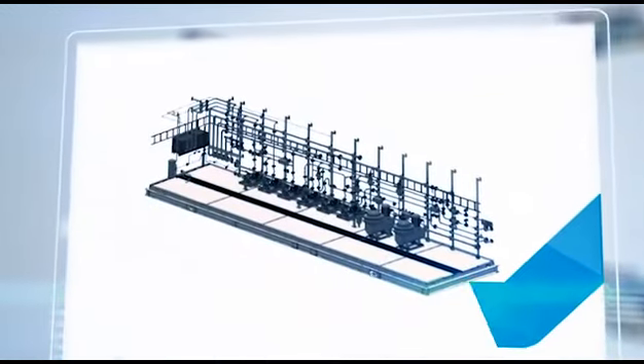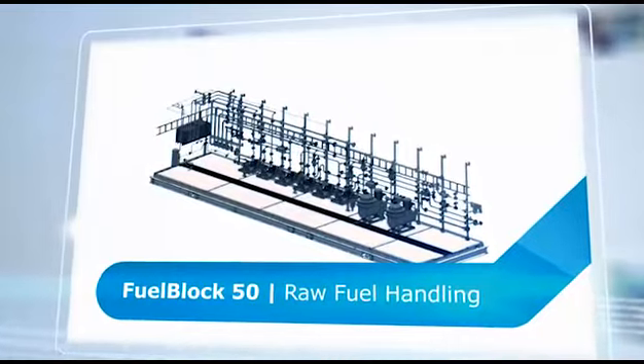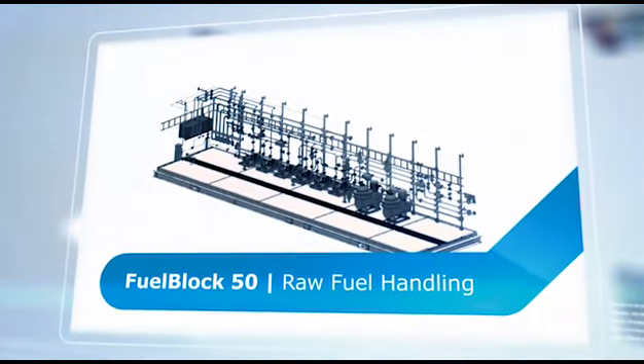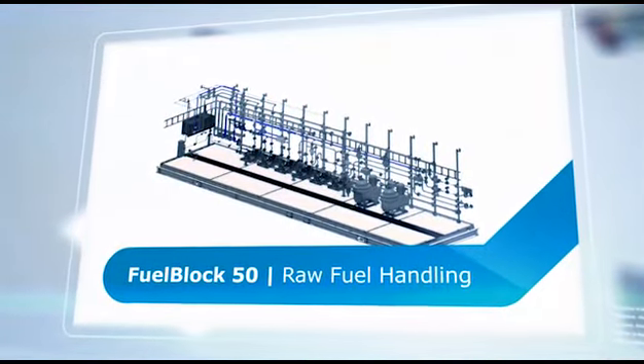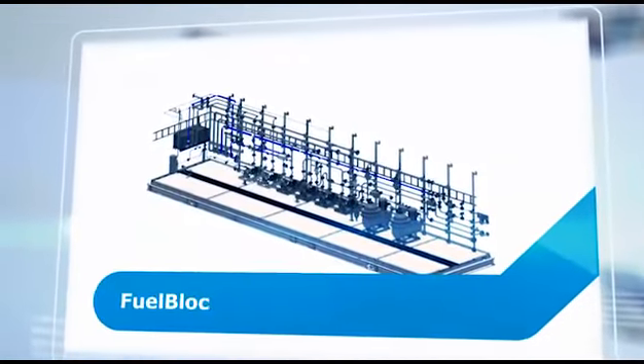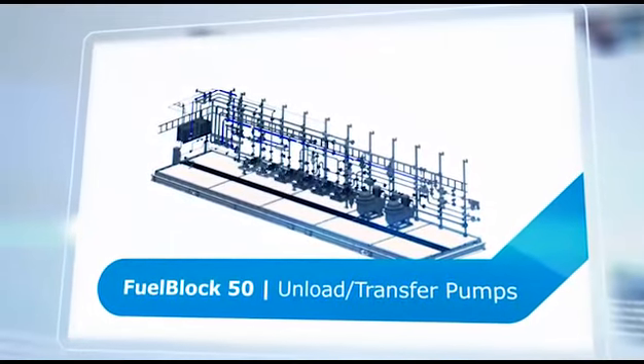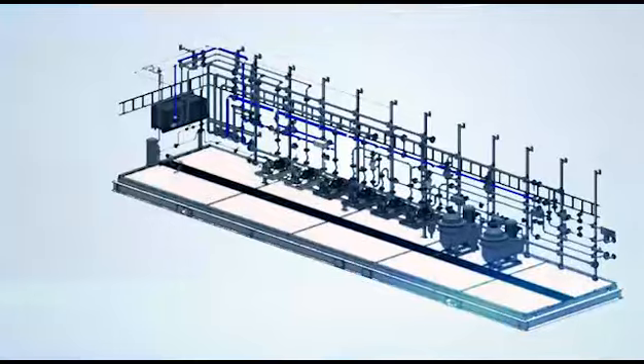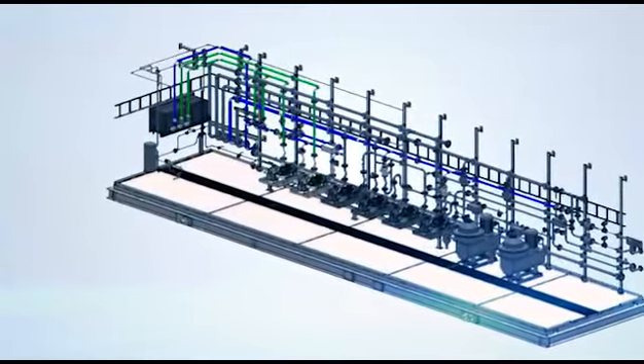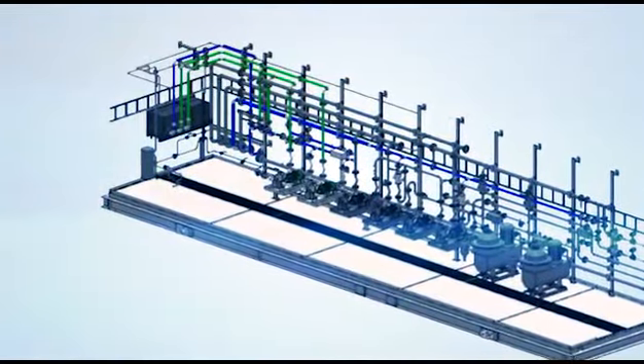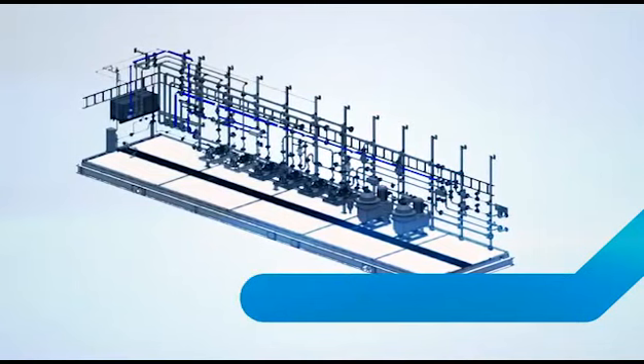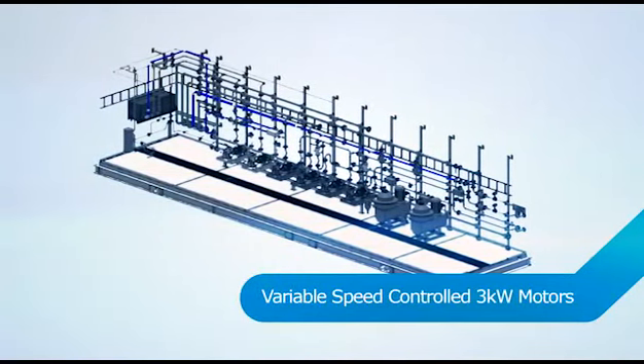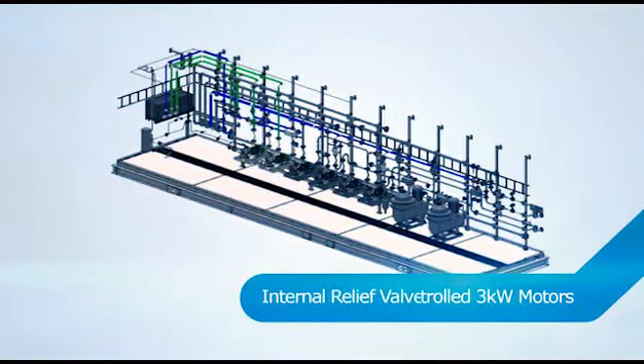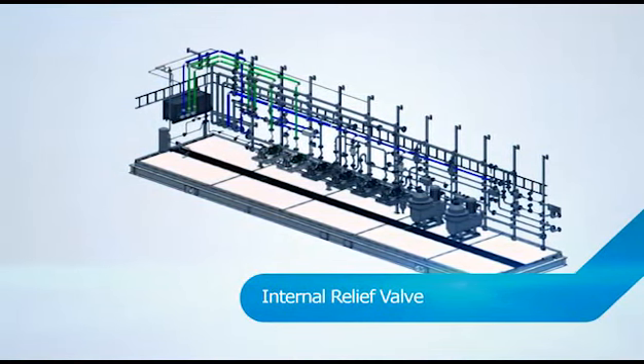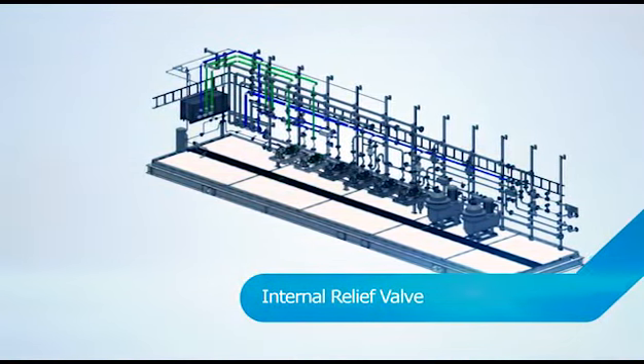The fuel block is able to receive raw fuel from tankers and/or dedicated bulk fuel tanks. The raw fuel is transferred to a dedicated raw fuel tank. Pumps are optionally available to facilitate tanker unloading or bulk fuel tank transfers. Vane-type positive displacement pumps are employed for all fuel block transfer operations. The pumps are direct coupled to variable speed controlled 3 kilowatt electric motors. An internal relief valve protects the pump and downstream piping.